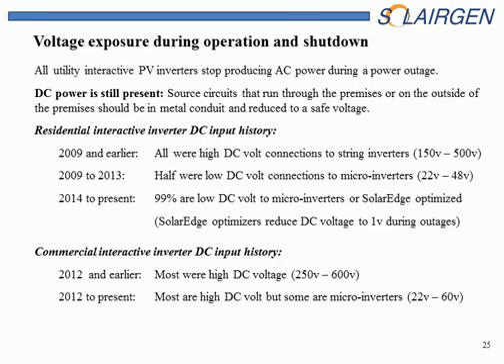On commercial interactive inverters, it's a little bit different. We do have some microinverters on commercial systems, but they're more expensive and so they're not hitting that market as strong. 2012 and earlier, most were high voltage, 250 volts up to 600 volts. 2012 to present, we still have the high voltage. However, even though it's a high voltage string inverter, the inverters are actually located where the PV array is. So we're not looking at conduits running all the way down to the ground like we did before 2012, which was typical. We're seeing these inverters being mounted where the PV array is. So we have a little more safety in the commercial system in that it's contained to the PV array location.